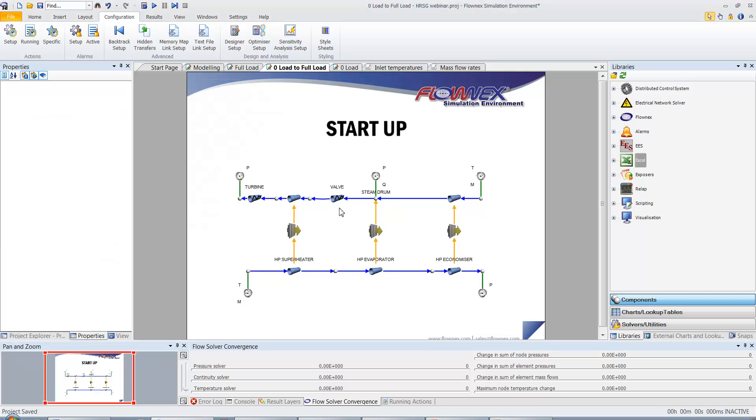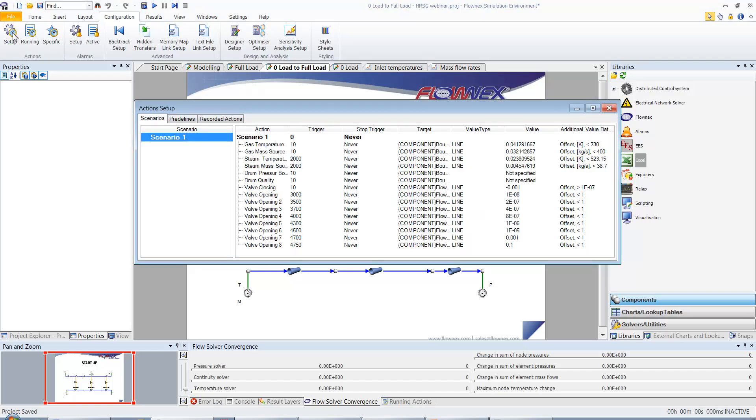We could now run the transient simulation by setting up actions under the configurations tab. The actions include varying the inlet properties on the gas and steam side as they would during start-up as well as the valve opening to control the level of the steam drum.